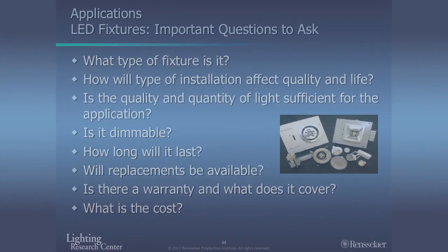Well, let's say a year from now, you have 3 fixtures that burn out, and you bought the best LED fixture, LED fixture 105. And now all they're offering is LED fixture 205. Well, it has twice the light output in a different configuration than your 105s. You try to stick that in your ceiling, it's going to look funny. So does it mean you have to buy 10 extra fixtures? Some manufacturers are actually recommending that. But you may want to ask your manufacturer, what's your guarantee that I'm going to be able to replace this with the same thing? And then what's the cost going to be?